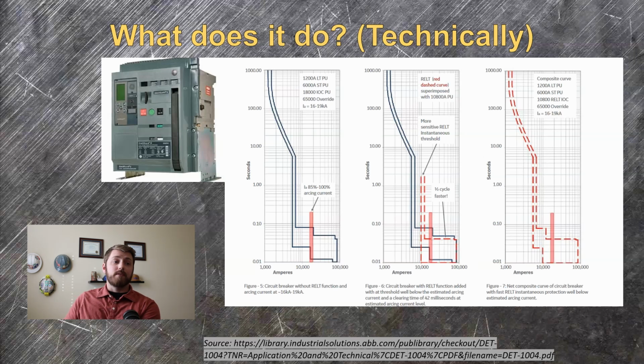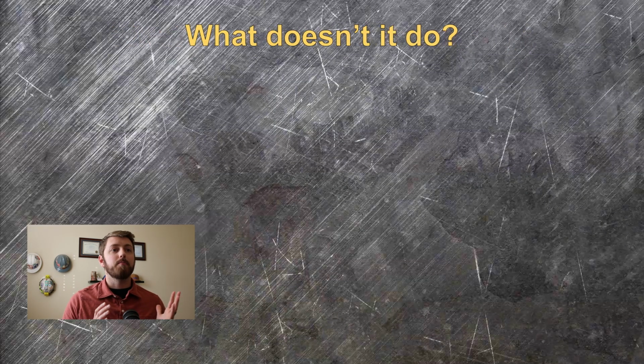That can be the difference between needing to change your pants and having a closed casket funeral after an arc flash. We need to have a strict understanding of what maintenance mode does and doesn't do. Number one, if the system isn't set up and commissioned correctly, it doesn't do anything. I've seen more than a few installations where a switchboard was shipped with all of the provisions for our maintenance mode system, even having the labeled maintenance mode switch on the front of the board, but the trip unit in the main breaker didn't have an input for the maintenance mode switch.